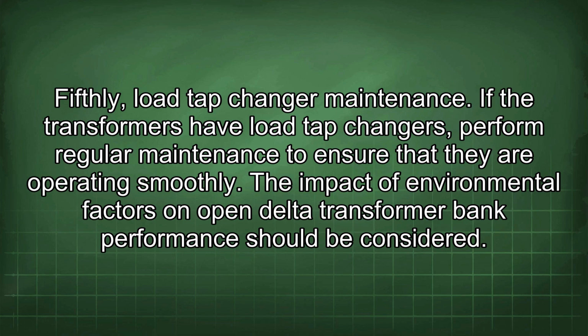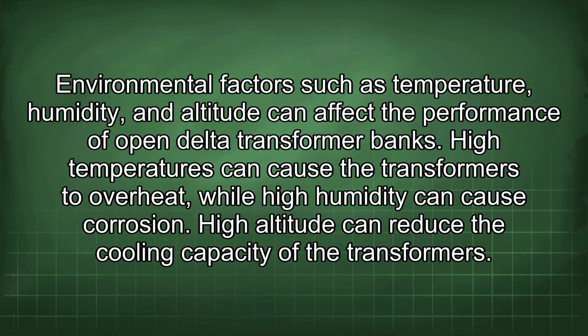The impact of environmental factors on open delta transformer bank performance should be considered. Environmental factors such as temperature, humidity, and altitude can affect the performance of open delta transformer banks. High temperatures can cause the transformers to overheat, while high humidity can cause corrosion. High altitude can reduce the cooling capacity of the transformers.